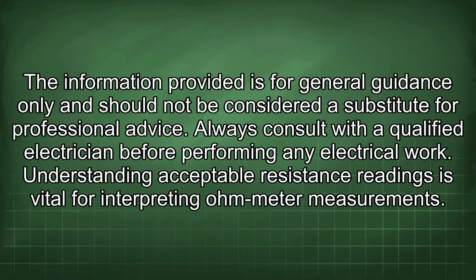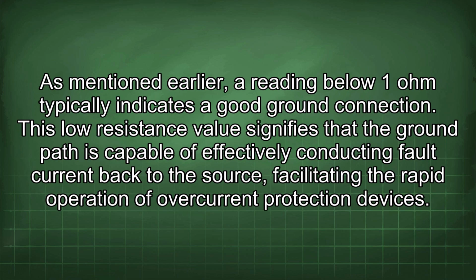Understanding acceptable resistance readings is vital for interpreting Ohm-Meter measurements. As mentioned earlier, a reading below 1 ohm typically indicates a good ground connection. This low resistance value signifies that the ground path is capable of effectively conducting fault current back to the source, facilitating the rapid operation of overcurrent protection devices.